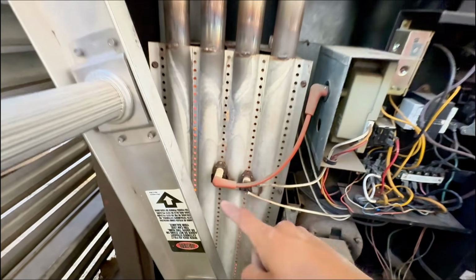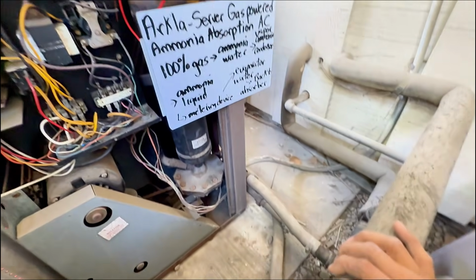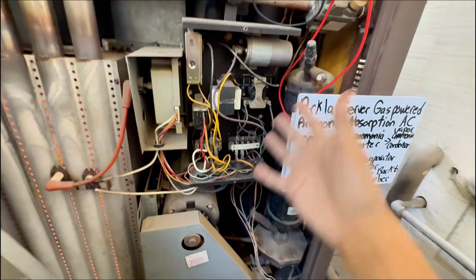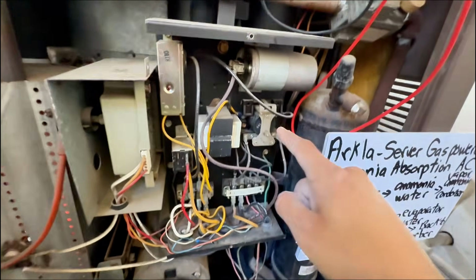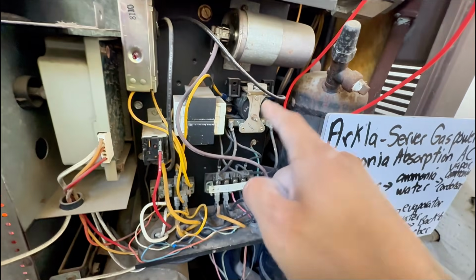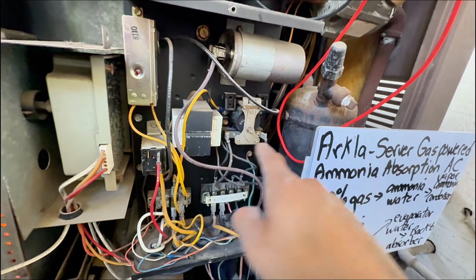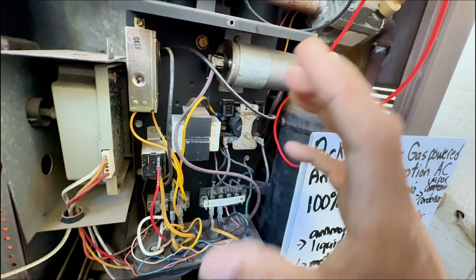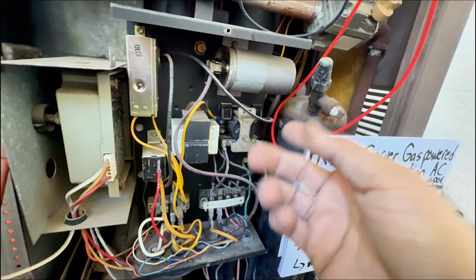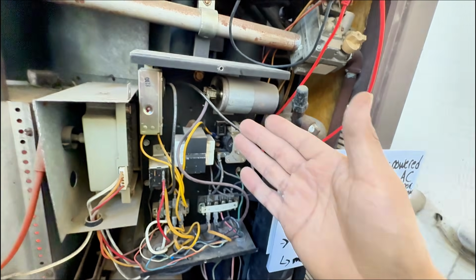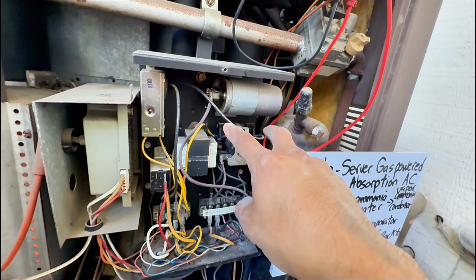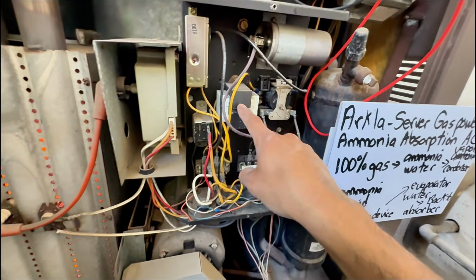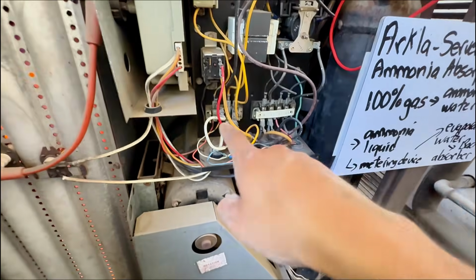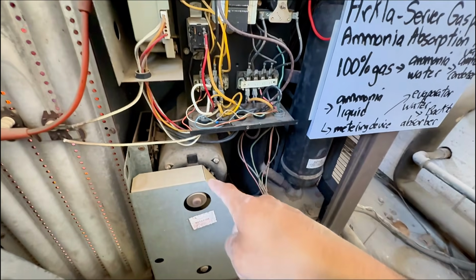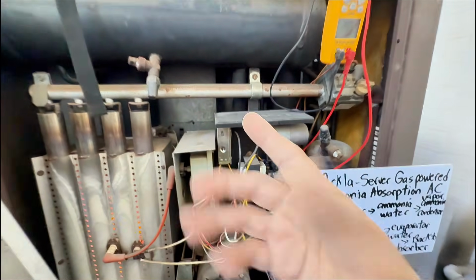Right now, you see, you got burners right there. So this is the electrical. You got a cap, which you're already used to seeing. And yes, guess what that is? That is a contactor. This is the open contact here, and this is the 24 volts. Crazy how they used to look back then. I don't know if it's called a contactor, but it's the same concept where it receives 24 volts and it closes the switch. You got a transformer, you got a relay, you got where your power comes in, you got a pump, you got a gas valve, and then you got a condenser fan right there.